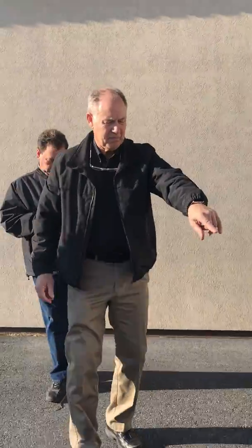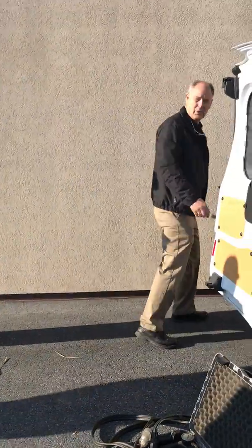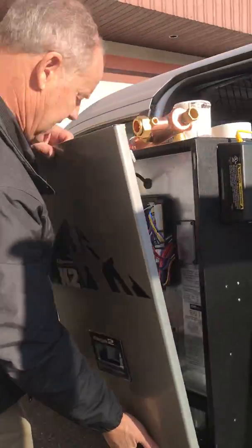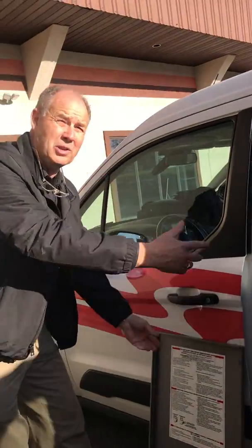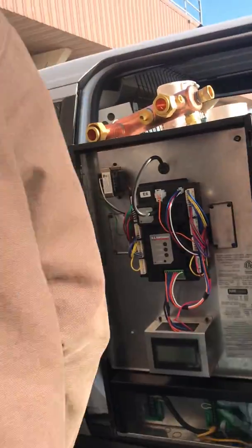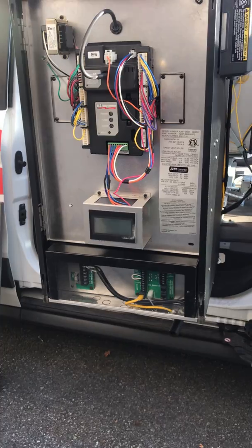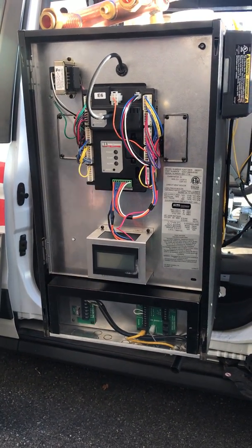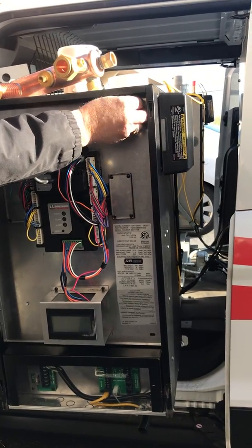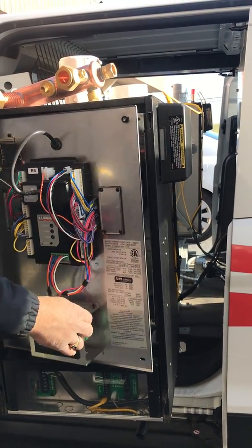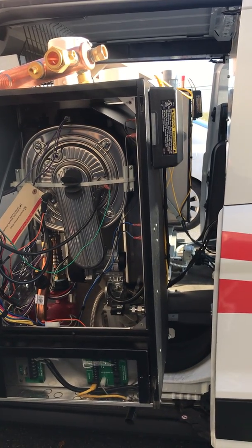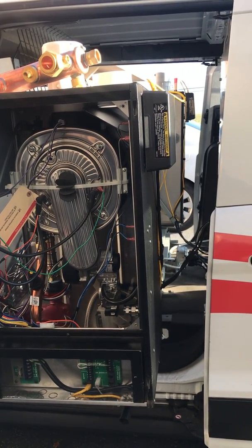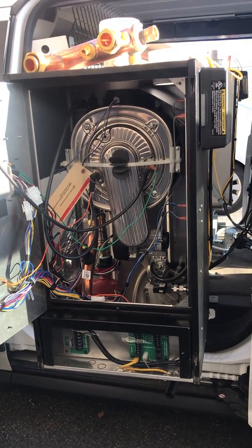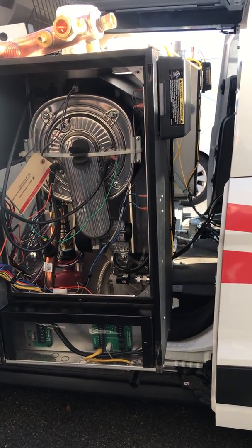Now, the same boiler over here with no domestic is our K-2 heating only. This one has a front cover that comes off, and this one has an access panel on the side. We lowered the cost on that one, so we took some cost out of it. They actually have the space in between in here. Now you can see that looks a lot easier to service, doesn't it? There's not as much in there. This one, we want to have 2-foot clearance on this side so that we can get into it.